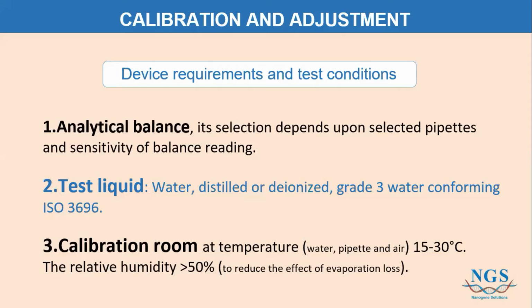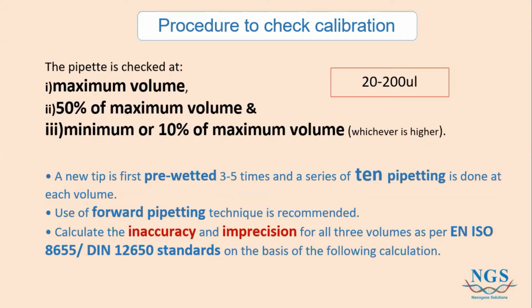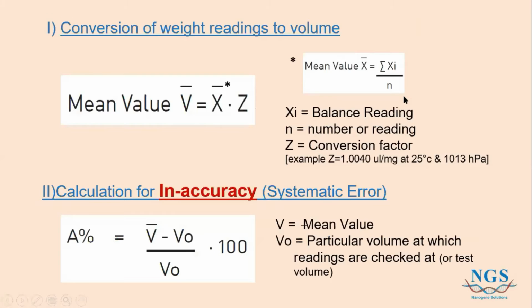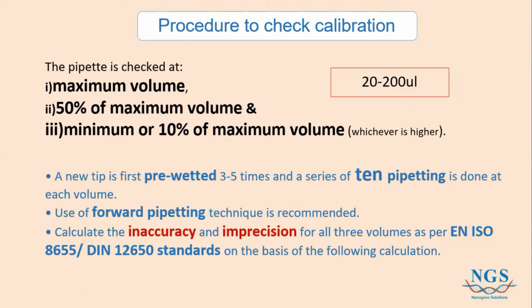All right. Okay, hold on. All right. So you have all your instruments and you're ready, you have the room. All right, so you want to move on to checking your calibration. So with the pipette, there are actually 3 checking volumes that you need to know. So for example, I was using a 20 to 200 microliter volume pipette. So let's use that as a guide. So 3 checking volumes. The first checking volume would be the maximum volume of your pipette. So my maximum volume would be 200 microliter. All right. So the second checking volume would be 50% of the maximum volume. So 50% of 200 microliter would be 100 microliter. And lastly, you will be using the minimum volume, which, in my case, would be 20 microliter.